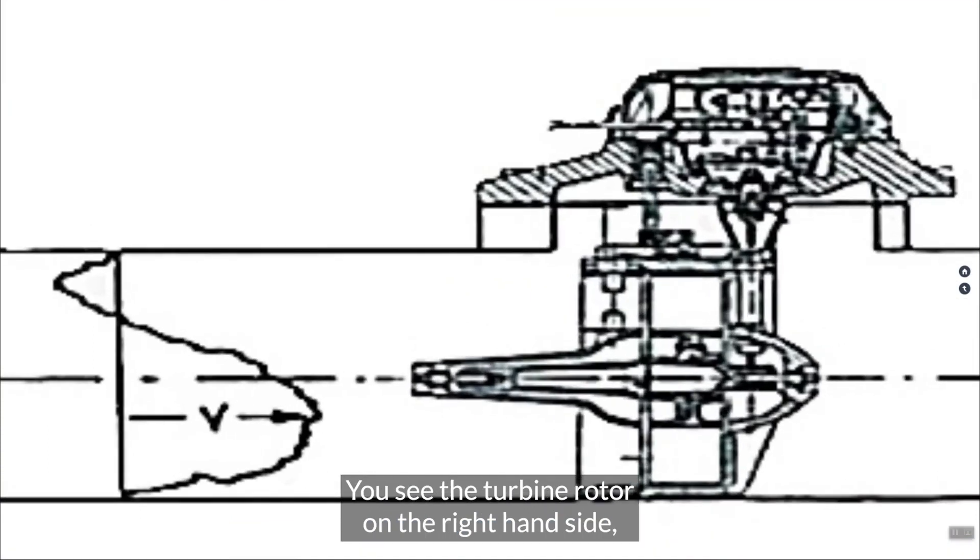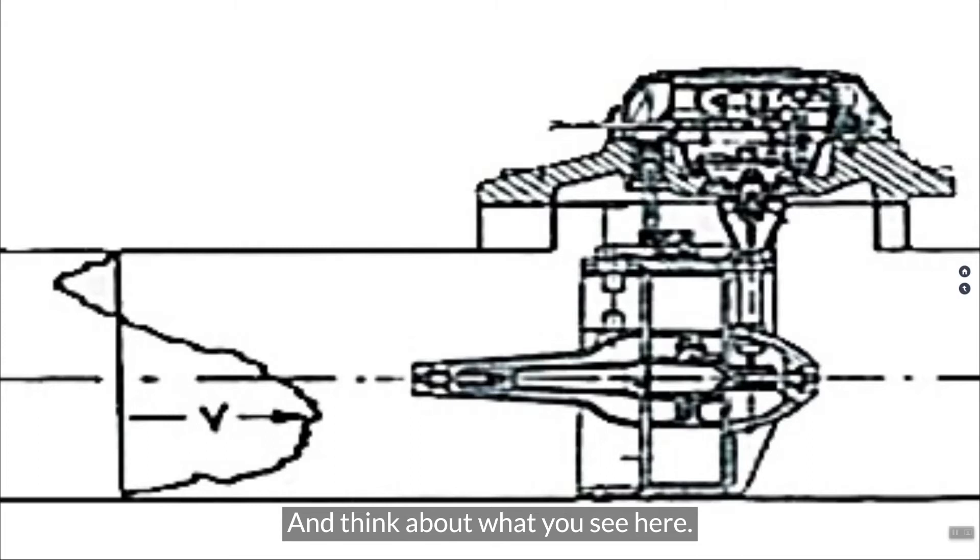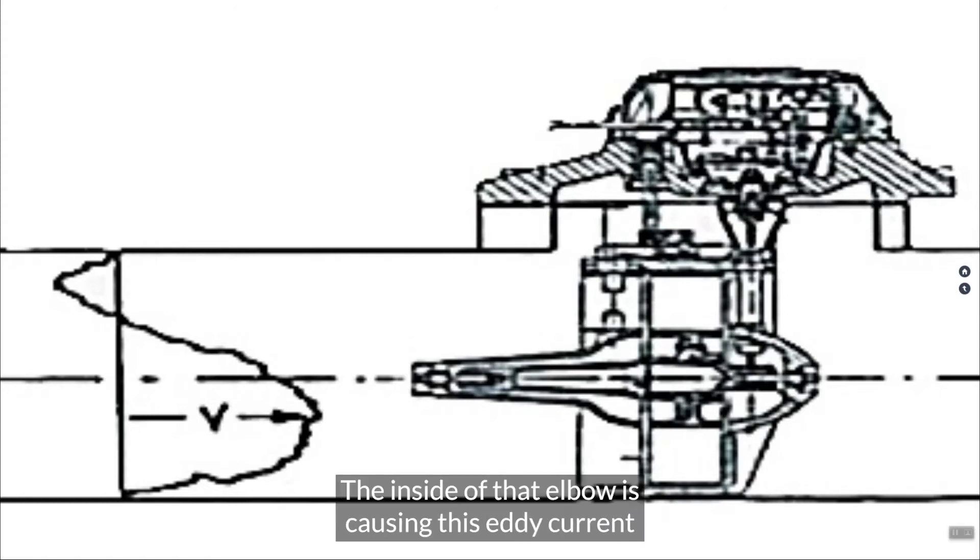If we take a closer look at this, this is what's happening. You see the turbine rotor on the right hand side. The left-hand side shows you that velocity profile. And think about what you see here. Towards the top quarter of the pipe, you actually have a reversing of flow. You have an eddy current effect here. The inside of that elbow is causing this eddy current, meaning that as it approaches the turbine element, it's almost trying to make that turbine blade go in reverse.